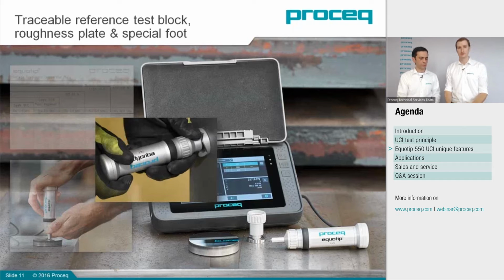It further helps reduce vibrations caused by the user, since you have to apply up to 50 newtons of test load, which could cause certain vibrations in the probe. With this foot, that can be significantly reduced. A third nice advantage is that the diamond indenter is protected, avoiding damage. You can also see the magnets on the flat surface, which help stabilize the probe when measuring on flat surfaces.